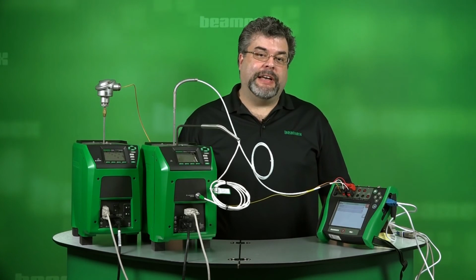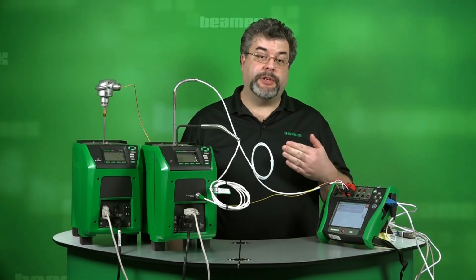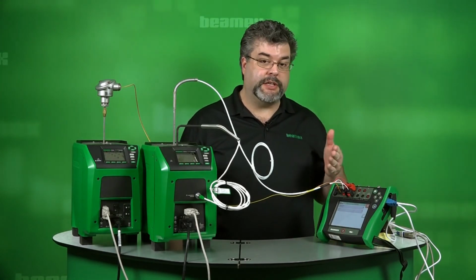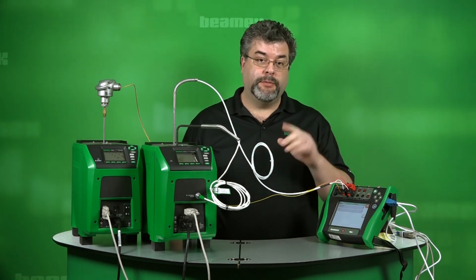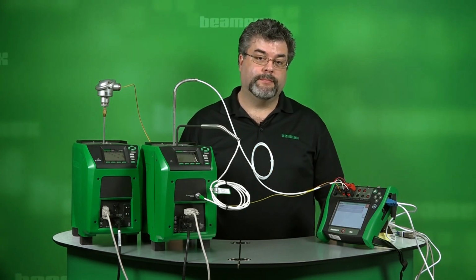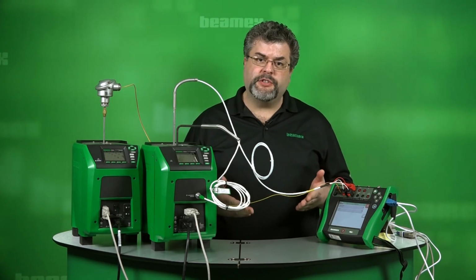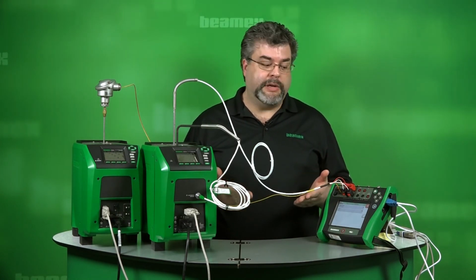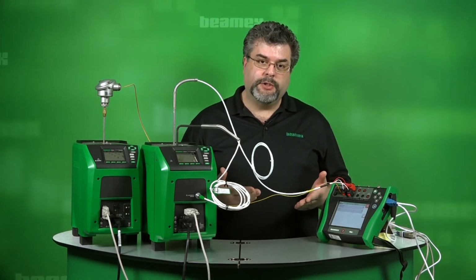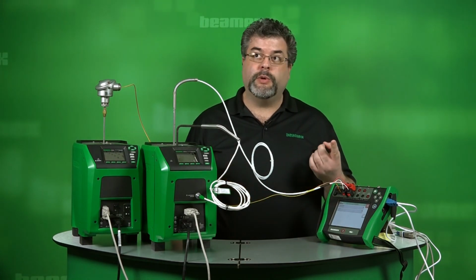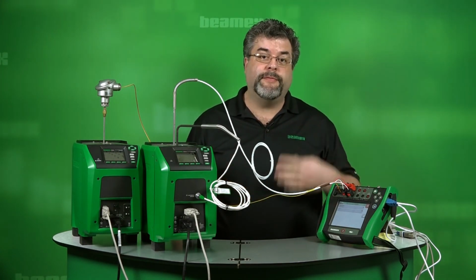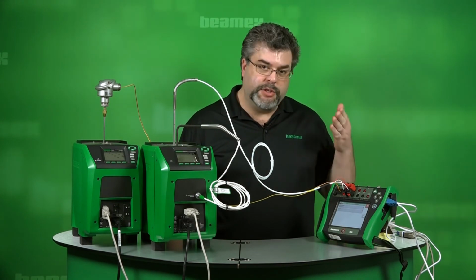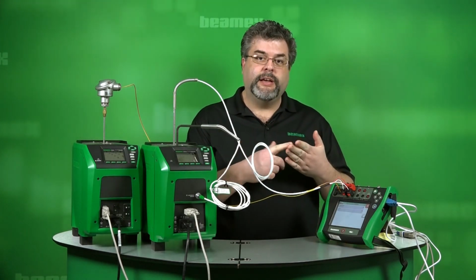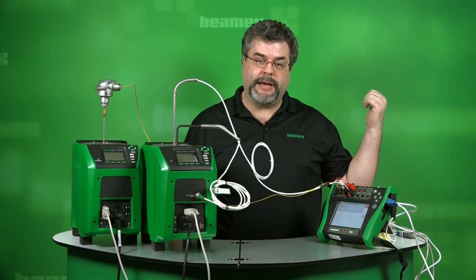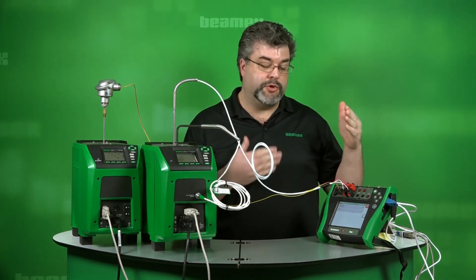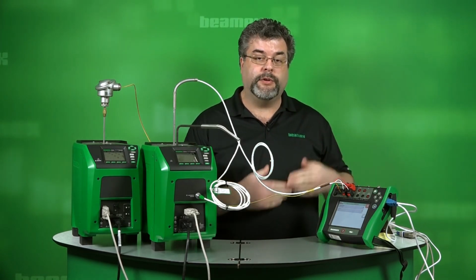So we've just finished an automatic calibration of 2 separate temperature elements using an MC6 and 2 different dry blocks with the push of 1 button. Now, you know now that this is automated. You don't have to be standing here watching it. So if you have a scenario to where you have to calibrate 1, 2, 3, or maybe 4 different temperature elements, you can set that up here, push a button, and maybe even leave for the day. Come back in the morning, your data will be captured and stored in the calibrator, waiting for you to grab it.